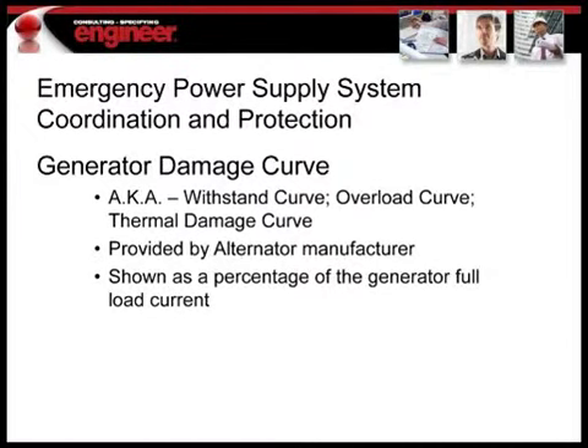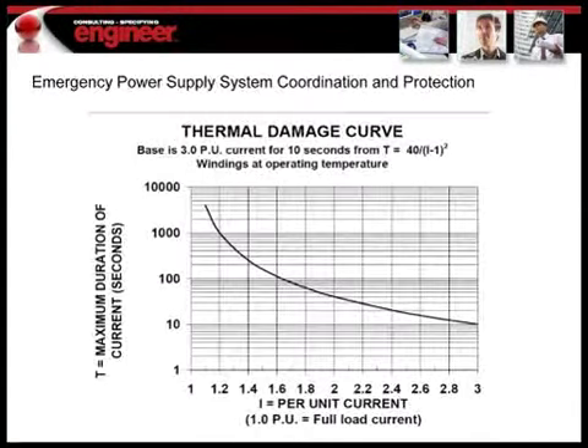Typically this is shown as a percentage or a per unit value of the generator full load current. This is an example of a thermal damage curve from one of the major manufacturers for alternators. As you can see at the bottom, it's talking about 1, 1.2, 1.4. That would be times the full load current, so it's pretty straightforward math. Typically they have a damage curve that applies to all alternators of the same frame type. So you might have a 1500 kW and a 1750 kW that have the same exact damage curve. It might look exactly the same. It's just that the full load current changes, so it gives different values. Now, remember that this line shown here is the point at which that alternator would actually be damaged. So this is a critical line to get right, to make sure that we model it and don't let any of the breakers or the current exceed this value and cause damage to our units.